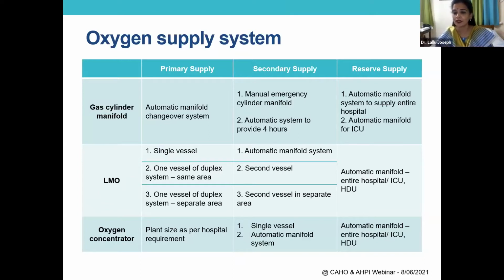Now, if you are a large hospital, you have an LMO. You may be a 300-bedded hospital, you may have a single vessel. You may be a 600-bedded hospital, you may have 2 vessels. You may be a 3,000-bedded hospital, you may have 2 separate vessels in 2 separate areas. So these are the 3 scenarios I've put together. If you're a single vessel, then what happens? You need to have a manifold as a backup. Then the reserve supply there can be a manifold again, or just your ICU connected to your manifold.